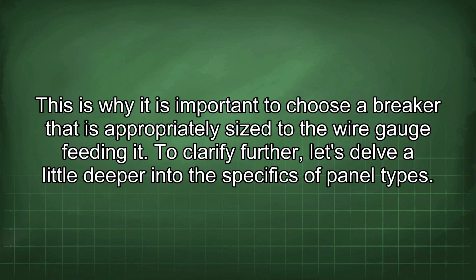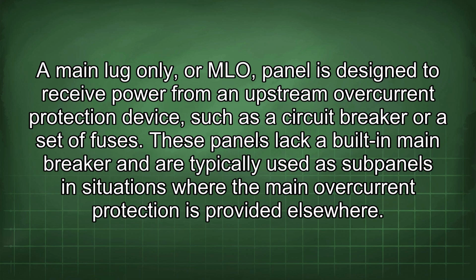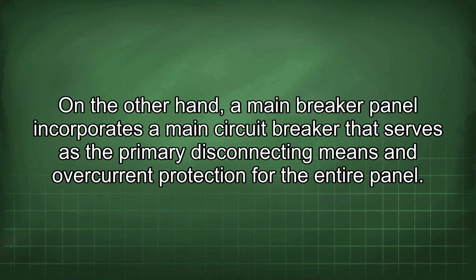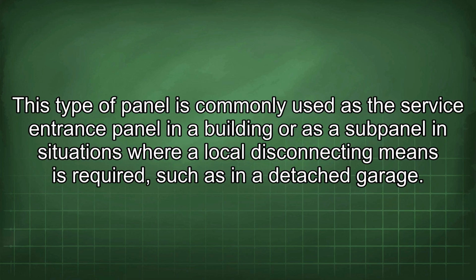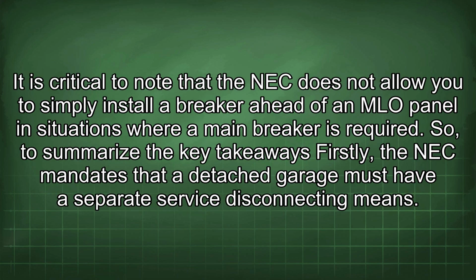To clarify further, let's delve a little deeper into the specifics of panel types. A main lug only, or MLO, panel is designed to receive power from an upstream overcurrent protection device such as a circuit breaker or a set of fuses. These panels lack a built-in main breaker and are typically used as subpanels in situations where the main overcurrent protection is provided elsewhere. On the other hand, a main breaker panel incorporates a main circuit breaker that serves as the primary disconnecting means and overcurrent protection for the entire panel. This type of panel is commonly used as the service entrance panel in a building or as a subpanel in situations where a local disconnecting means is required, such as in a detached garage. It is critical to note that the NEC does not allow you to simply install a breaker ahead of an MLO panel in situations where a main breaker is required.